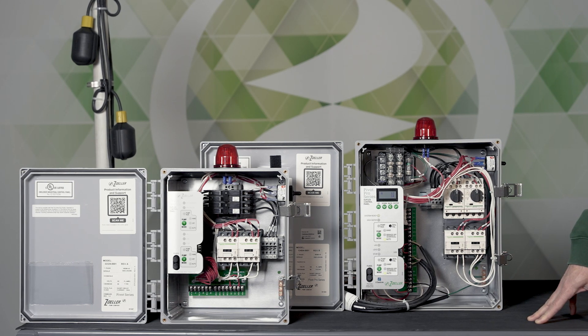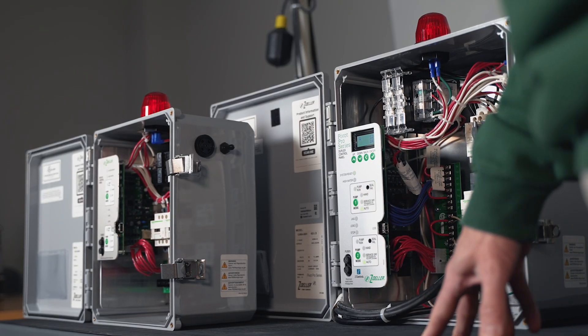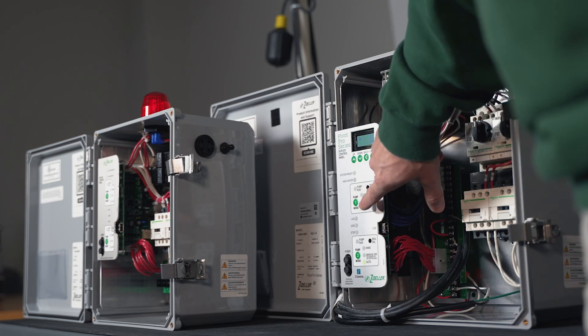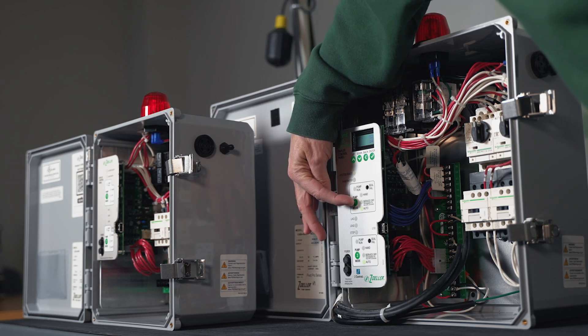There's an even bigger problem with either a burned out pump or a pump that needed to turn on but couldn't because it was in the wrong mode. So what we've done with these HOAs — we call them smart HOAs — is that you can toggle with this button right here through the modes. You may or may not be able to see me doing this, but when you push the button...